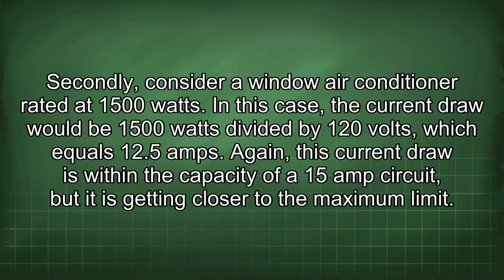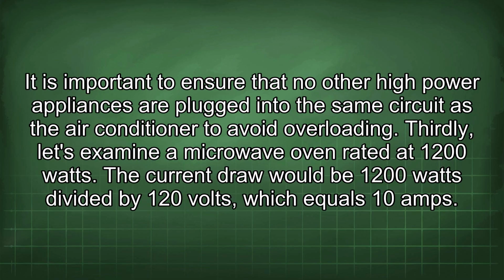Secondly, consider a window air conditioner rated at 1500 watts. In this case, the current draw would be 1500 watts divided by 120 volts, which equals 12.5 amps. Again, this current draw is within the capacity of a 15 amp circuit, but is getting closer to the maximum limit. It is important to ensure that no other high power appliances are plugged into the same circuit as the air conditioner to avoid overloading.